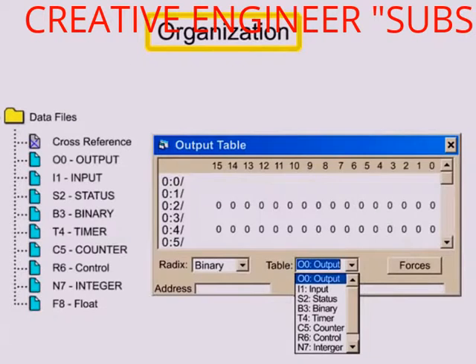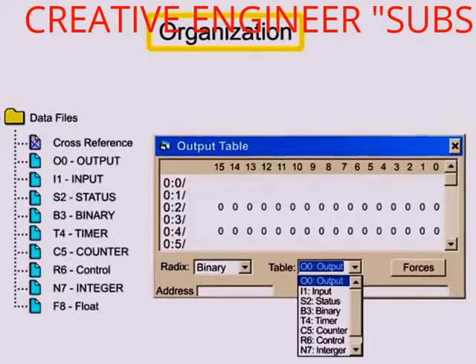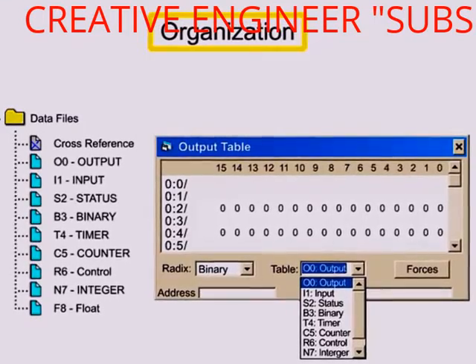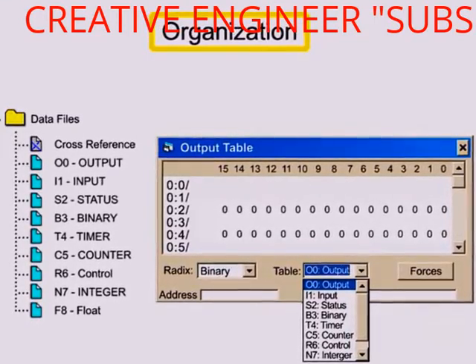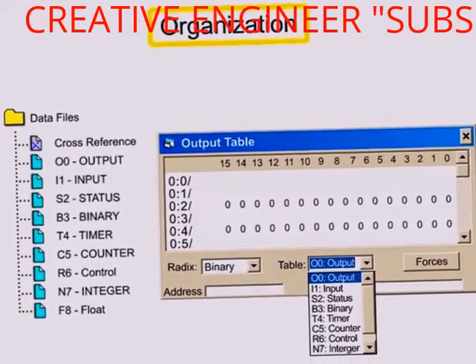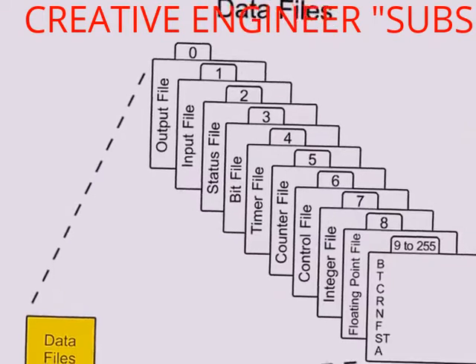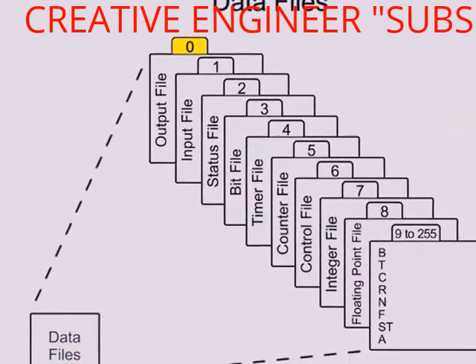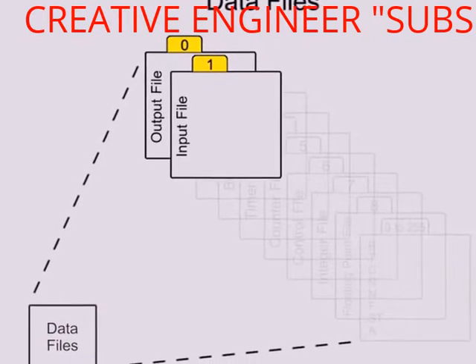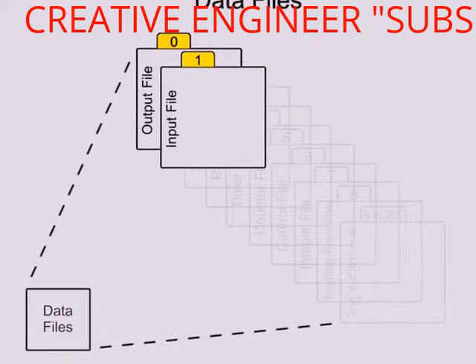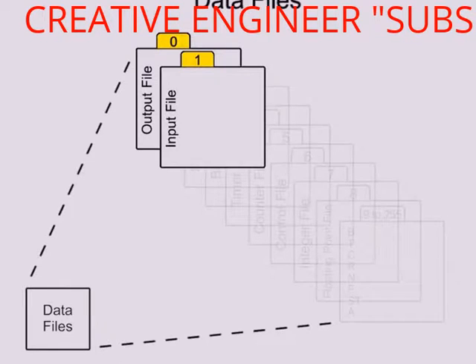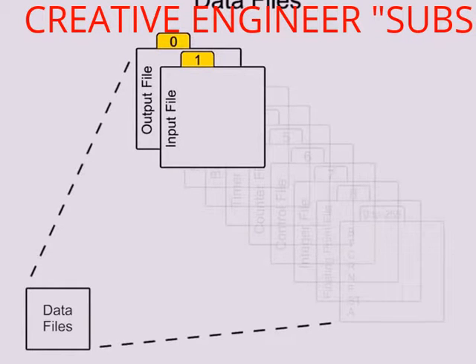Organization is defined by the type of data they contain and are assigned a file number. Files 0 and 1 are input and output data files assigned to a physical location of a rack and slot providing an interface to real-world input-output.